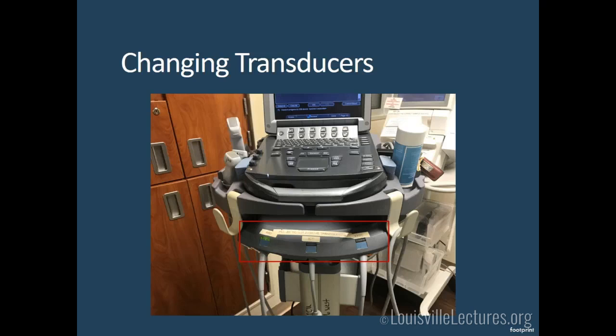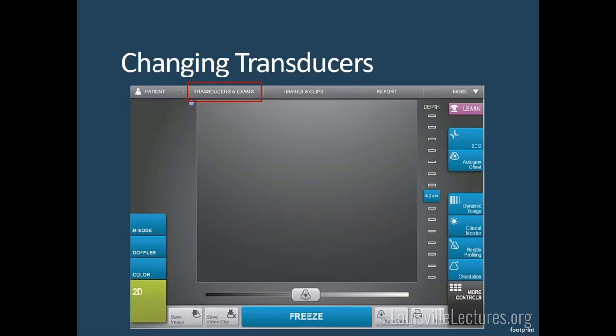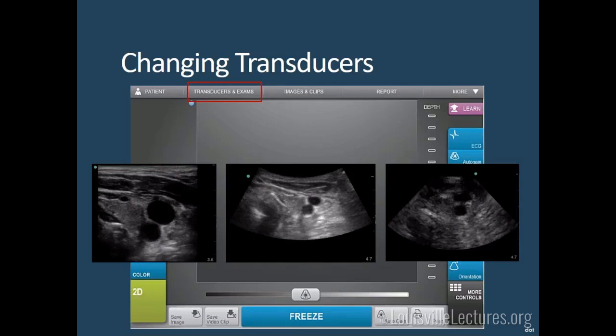Knowing how to change transducers is important. On old machines, you use the module underneath to click and change probes. On the newer machine, there's a 'transducers and exams' tab on the touchscreen that gives you all probes with images — easy to switch through. When you switch probes, the footprint and image change significantly. I use the footprint to know which probe is selected even if I haven't checked the screen.